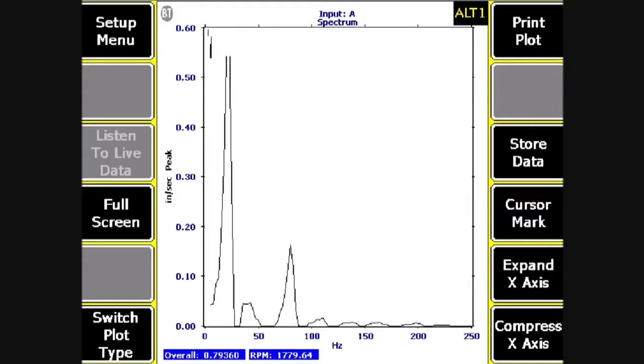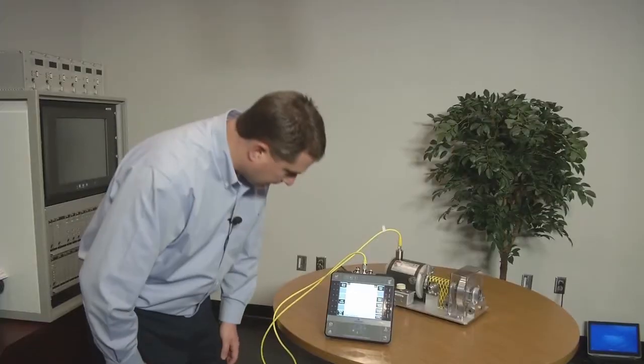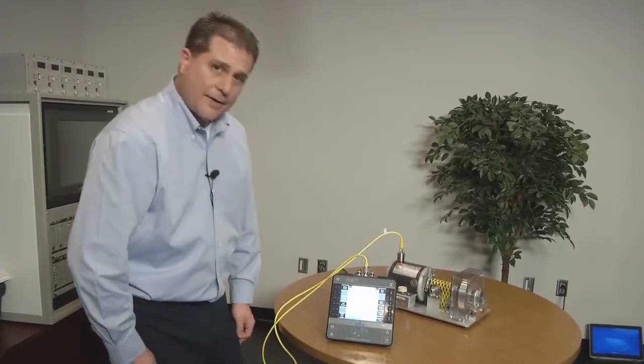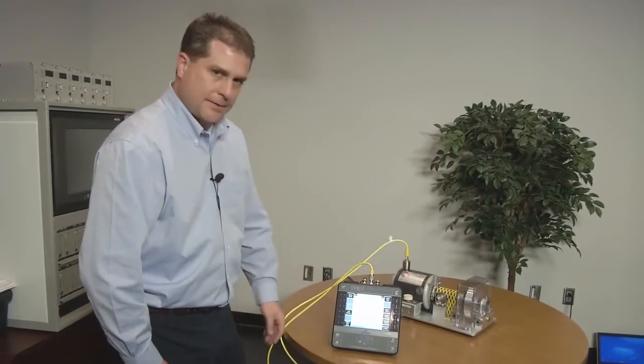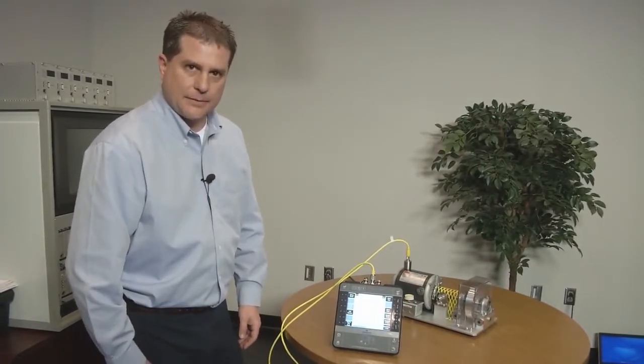So now this large peak that you see here should be the resonant frequency as a result of the impacting that we just did. That is about 20 hertz. This machine, the running speed is 1,700 and something, so it's up around 30 hertz.